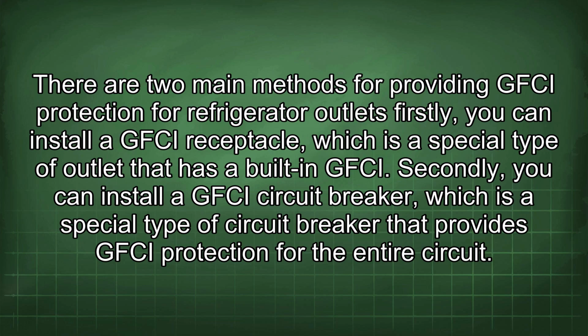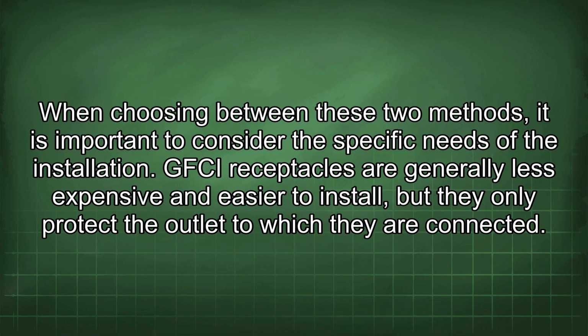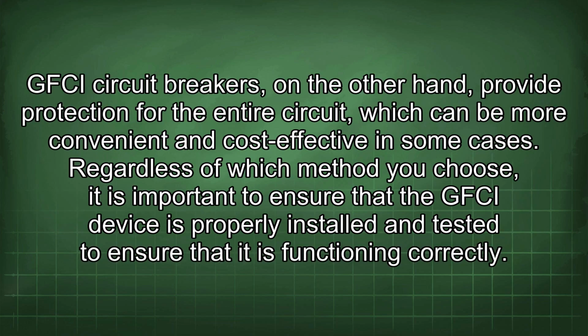Secondly, you can install a GFCI circuit breaker, which is a special type of circuit breaker that provides GFCI protection for the entire circuit. When choosing between these two methods, it is important to consider the specific needs of the installation. GFCI receptacles are generally less expensive and easier to install, but they only protect the outlet to which they are connected. GFCI circuit breakers, on the other hand, provide protection for the entire circuit, which can be more convenient and cost-effective in some cases.